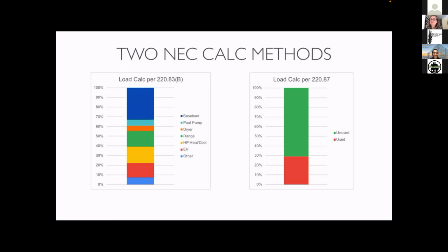The method on the left is 220.83b, which I'll call a bottoms-up calculation. It says go around the home, find all the nameplate ratings for the existing equipment, apply certain coincidence factors to each piece of equipment or type of equipment, then add in the equipment you'd like to add and see how close to your full panel capacity you come. Anything under your panel rating—say, 100 amps—when you add up your totals, if you're under 100 amps, you're good.